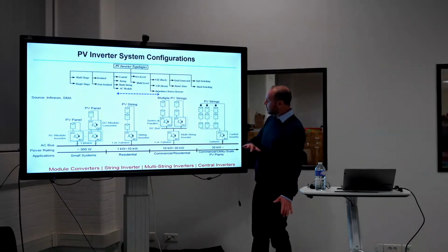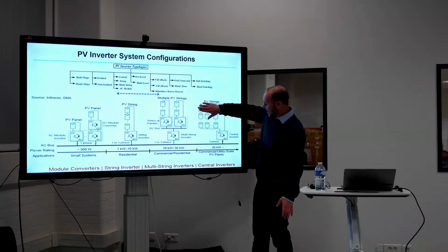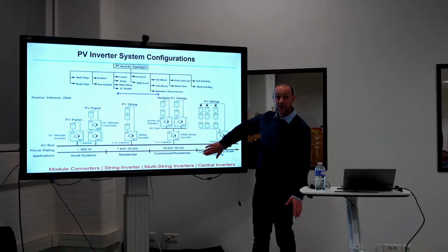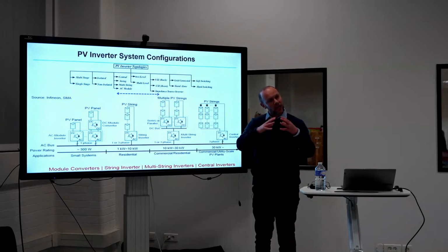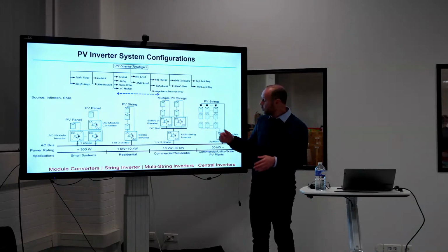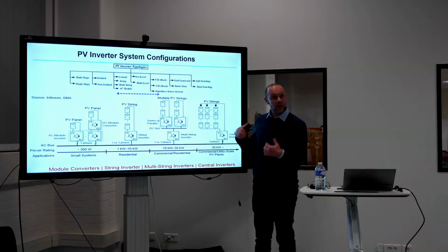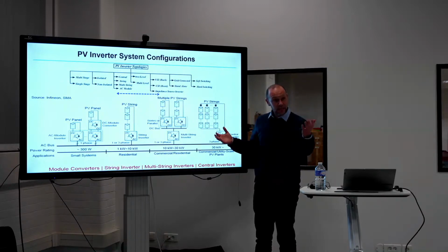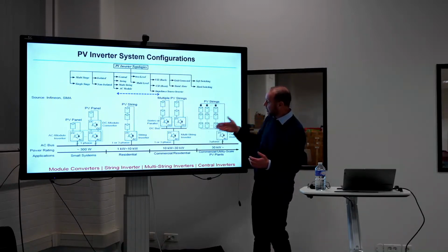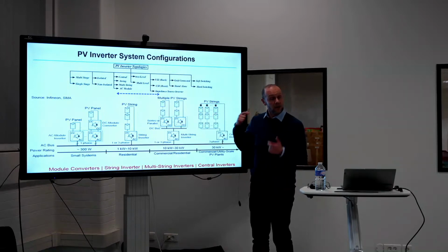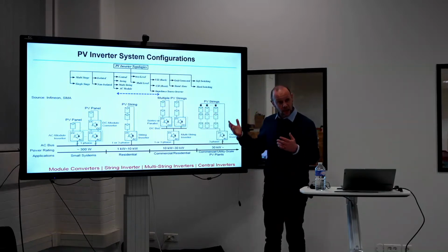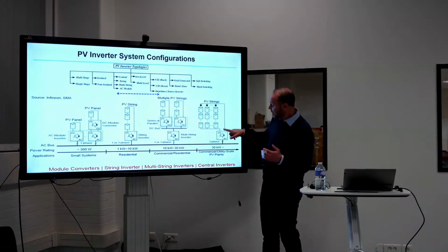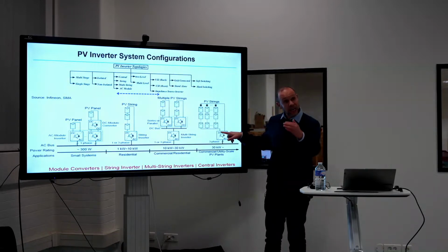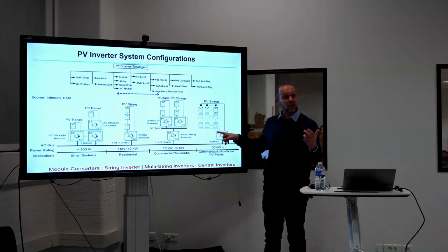What I said—this is the current central inverter setup used for large power plants, meaning megawatt-level plants use central inverters. One of the main issues, as I said, is that because these are connected in series and parallel, there are many other issues. For example, the voltage level is limited for safety reasons—you cannot increase beyond 1 kilovolt at the input of the inverter.